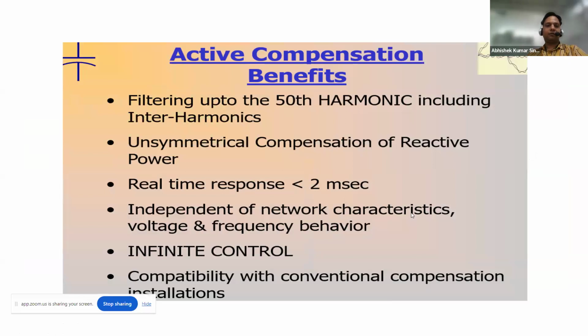Now basically the benefits of this active compensation. First of all, the first thing is the real-time compensation. The active filter compensates in real time, meaning wherever the harmonic is generated, it will immediately release the mirror image of that and definitely nullify the impact of that. There are multiple advantages of this active filter in the system. It can filter up to the 50th harmonic, and it takes very little space because they are just a box type system. You can place it in a very small space instead of the capacitors we have, because for capacitors we have to place huge panels. So we don't require that here. The response time is very low, less than 2 milliseconds, whereas in thyristor based it is almost 20 milliseconds, and in the capacitor it goes too high if we are having contactor based capacitors.